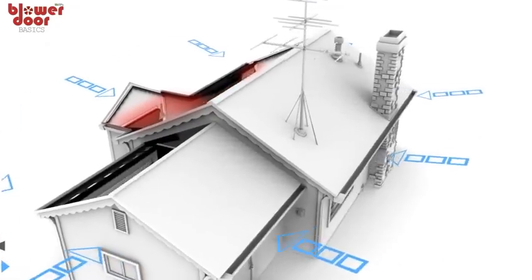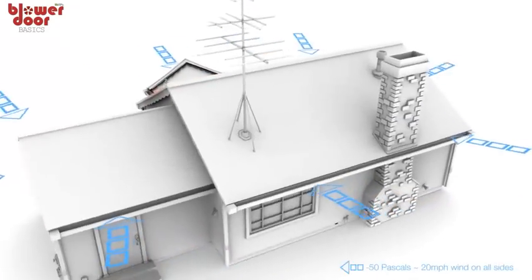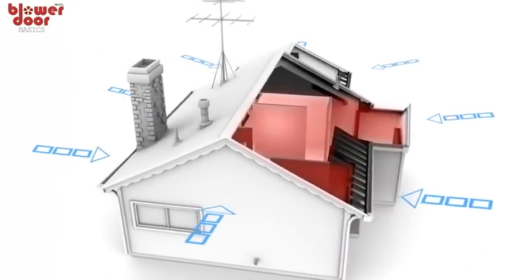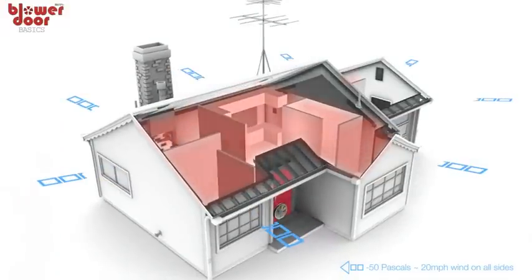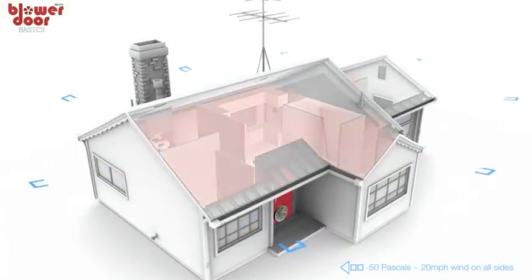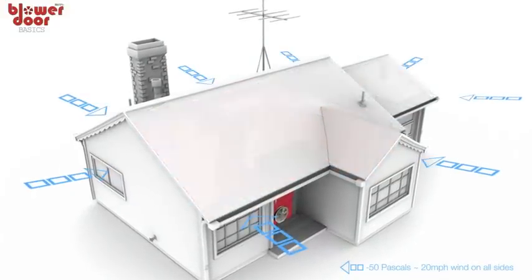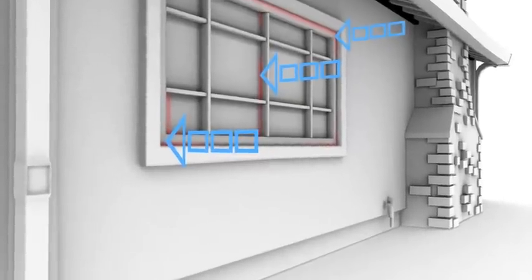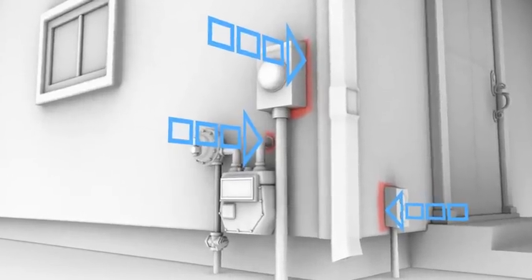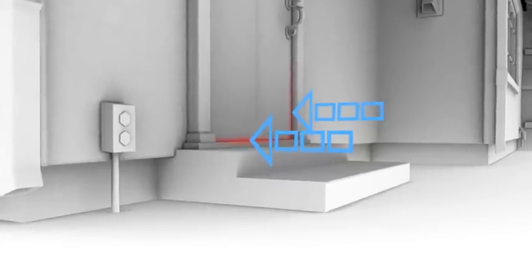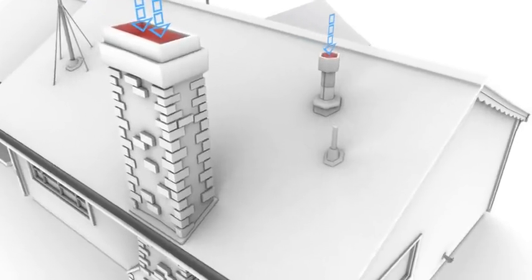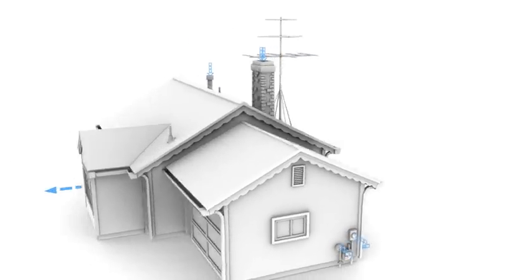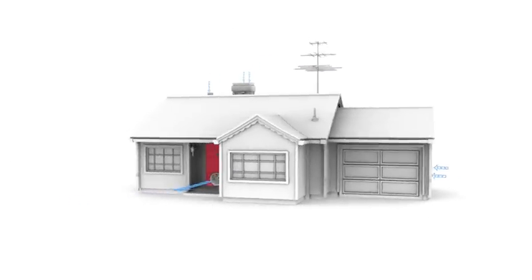Air wants to enter the home to equalize the pressures of the outside and inside environments. But instead of a natural wind pushing air inside the home, we are essentially using depressurization inside the home to suck air in through gaps in windows, pipe penetrations, improperly sealed doors, and leaky flue dampeners. These are the penetrations and gaps we look for when evaluating a home for air sealing measures.